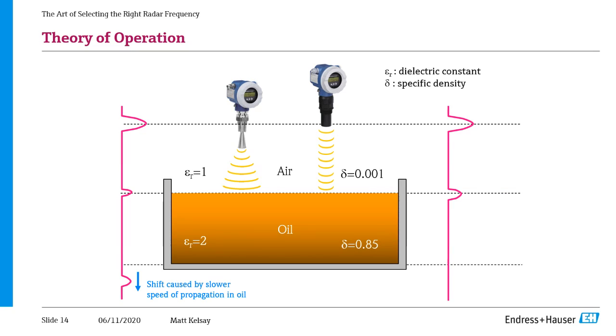Sure. So really, what we're looking at is a difference in either dielectric or density from air to the product you're measuring. So if you look at a radar device, the difference in dielectric from air, 1, to water, 80, is a very large difference in dielectric, meaning that you're going to get almost all of that signal reflected off the surface, come back to the radar, very easy to measure. If you look at oil, though, oil with a dielectric of roughly 2, that difference between 1 and 2 is now much smaller, so only a little bit of that signal is reflected, and some of it continues to travel through the product.